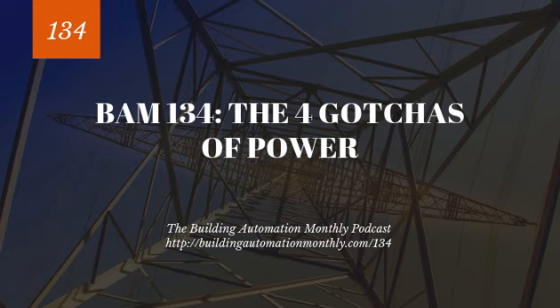When you go and do that, you run into gotcha number two, which is idle versus operated load. I don't know about you, but when I started off in this career, I really didn't grasp how VA loads were calculated, how volt ampere loads were calculated. I sat there and thought, man, why is a transformer 100 VA? I need 40 VA for my supervisory device, or 20 VA for my field controller. But what's the other VA for? What does that mean to me?